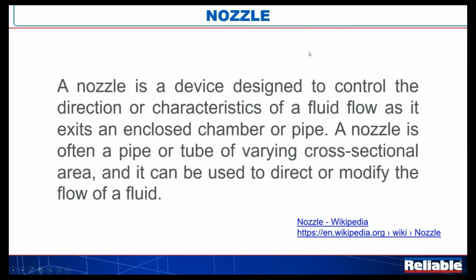So what's really the difference with the water spray system, right? Well, the primary difference is we're going to use a water spray nozzle. That's not to say we can't use a sprinkler, and we'll see how that's allowed in the standard. But you can see the definition on the screen. Everybody, I would presume by this point in their life, has held a nozzle at the end of a garden hose even. We should all know what a nozzle is and what it can do. We've all, hopefully, been around fire sprinklers and realized that they're essentially a nozzle with a thermal element in it. But what does it do? It's used to direct or modify the flow of a fluid, in this case, primarily water.